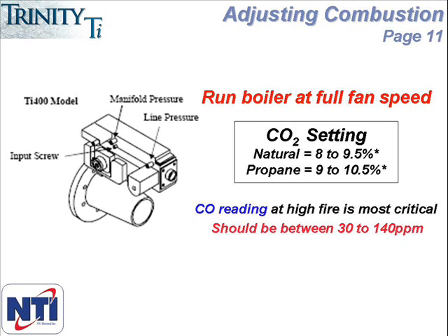That means four turns will take the valve back to its original position, and it takes two turns to go from completely open to completely closed and vice versa. The typical adjustment for the TI-400 is less than a quarter of a turn.